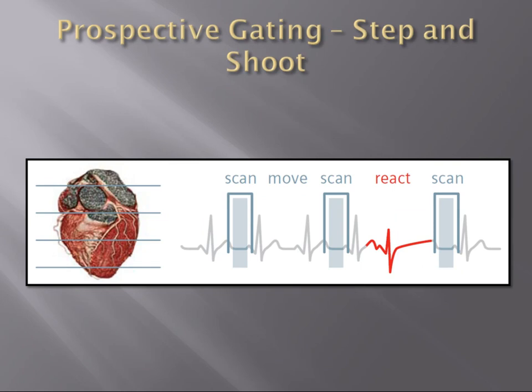Taking this a step further: since the sweet spot is the end-diastolic window, and we really aren't going to use the other phases — like the systolic phase with its motion artifact — for coronary imaging, instead of just reducing beam intensity during those other periods, what if we simply turned the beam off altogether? This way, we'd only be radiating the patient during that end-diastolic sweet spot, affecting even greater dose savings.